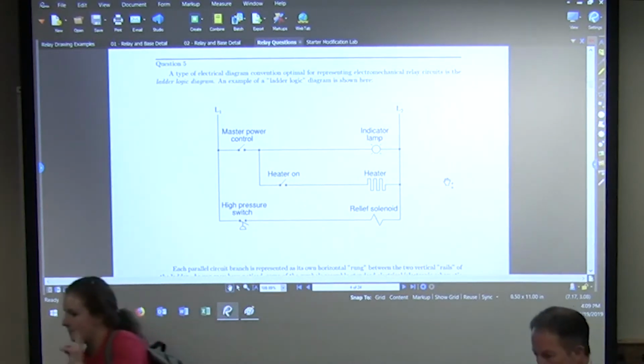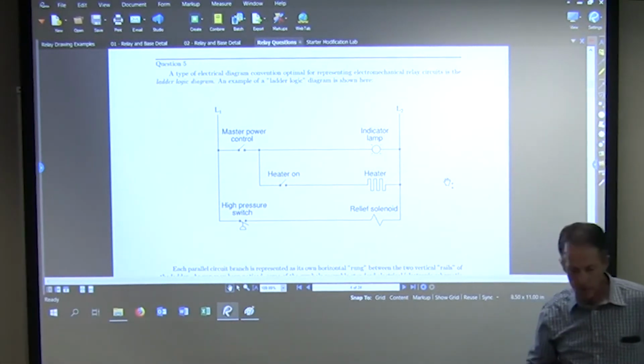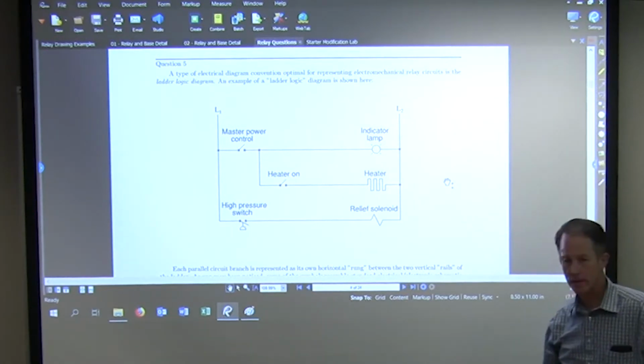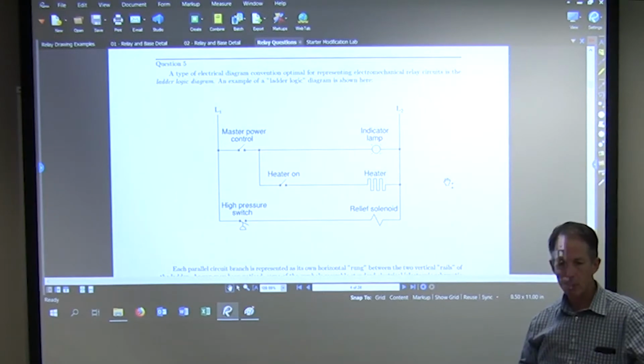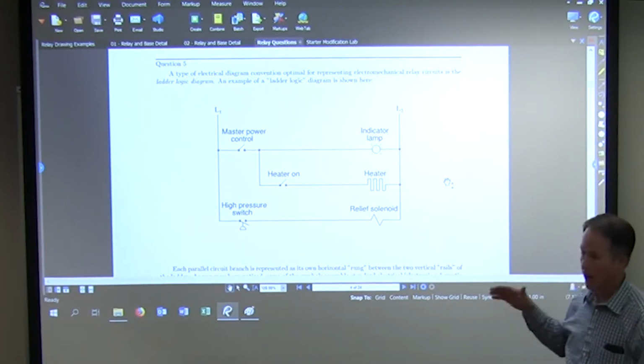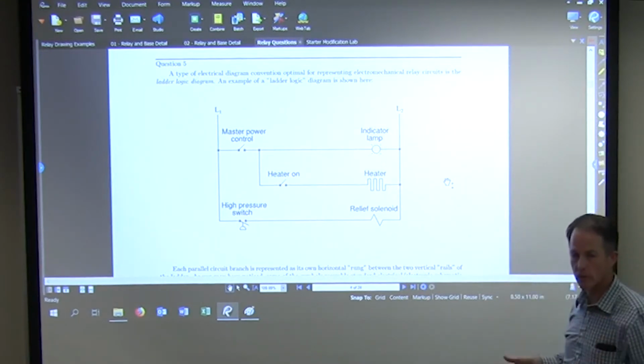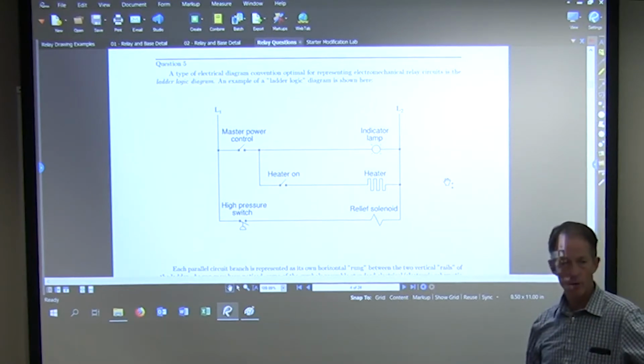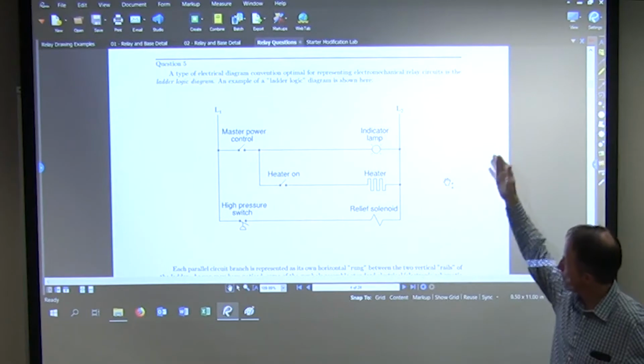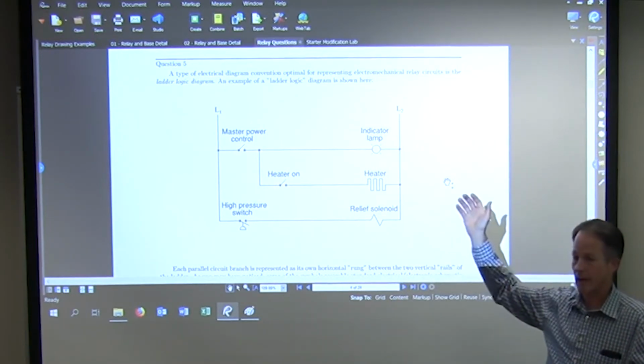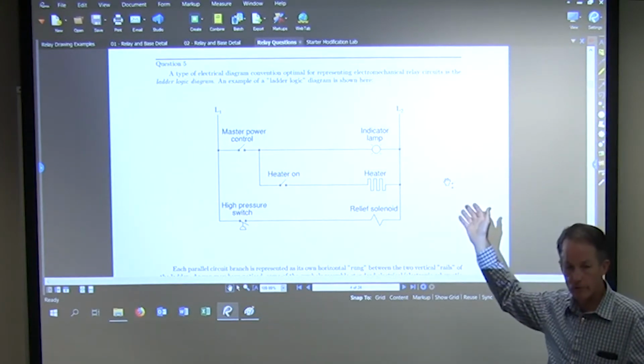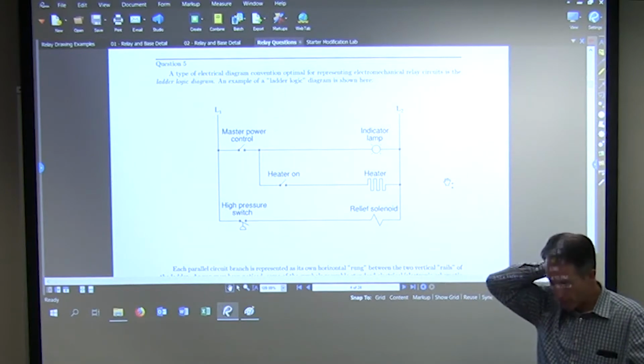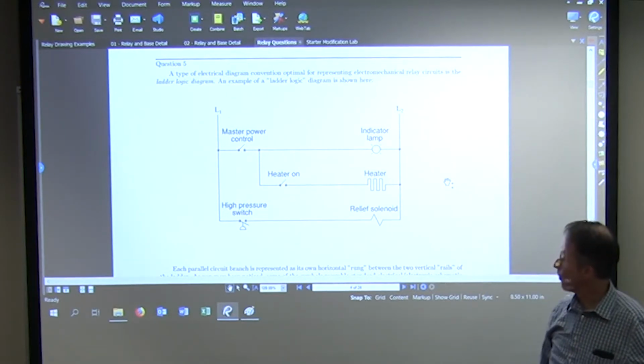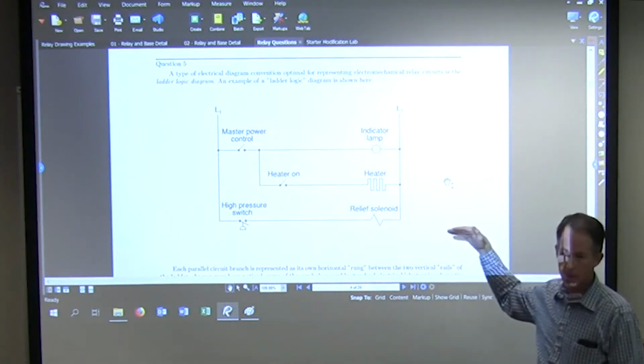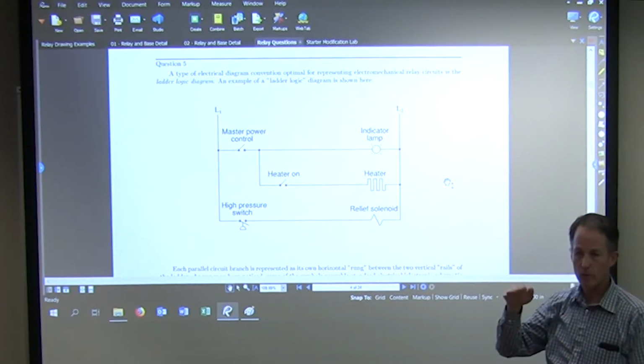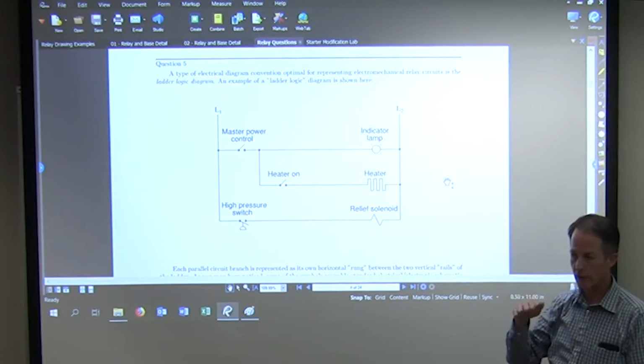A lot of times we have what we call ladder logic. Ladder logic is a way to isolate, control, kind of sequence, and to understand how it works. Our left and right vertical columns typically represent our voltages. So in this case, L1 is the left vertical line, L2 is the right vertical line. Those could be 120 and neutral, they could be 240 volt leg 1, leg 2, or a 480 volt circuit. All of the horizontal rungs, as they're called, represent the various control schemes, switching, and loads that we will then turn on and off.